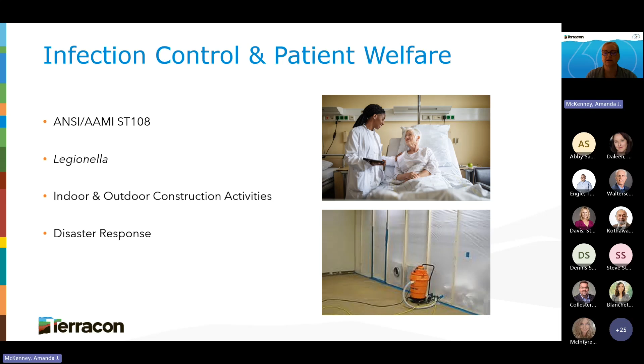Like I mentioned, the AAMI ST108 is considered industry standard. I do want to point out that it's not required by law, but adherence to this standard is considered a best practice and may be required for accreditation by organizations such as the Joint Commission. It only applies to water that touches your instrumentation. It's important to note there isn't a one-size-fits-all solution. It can be made facility specific and should be made facility specific.